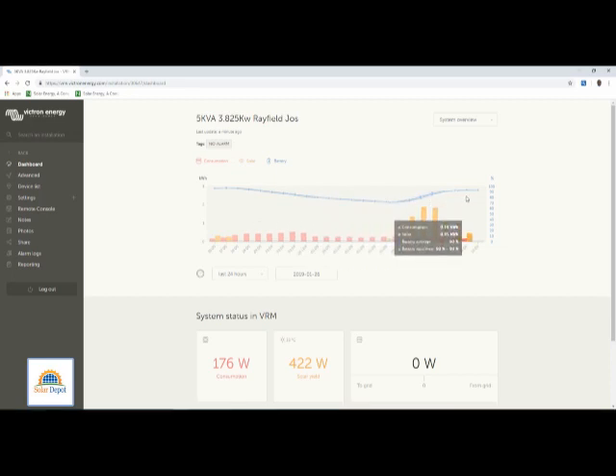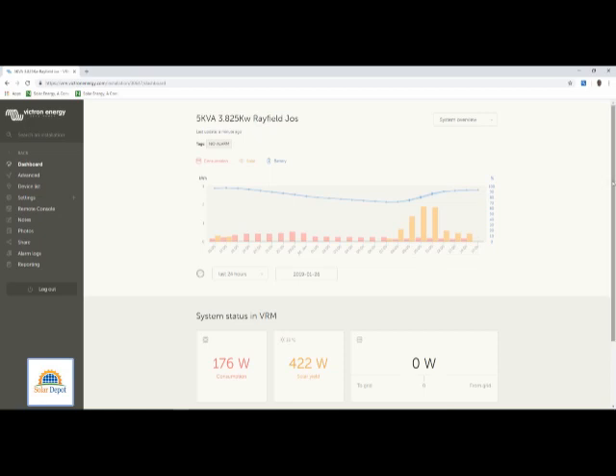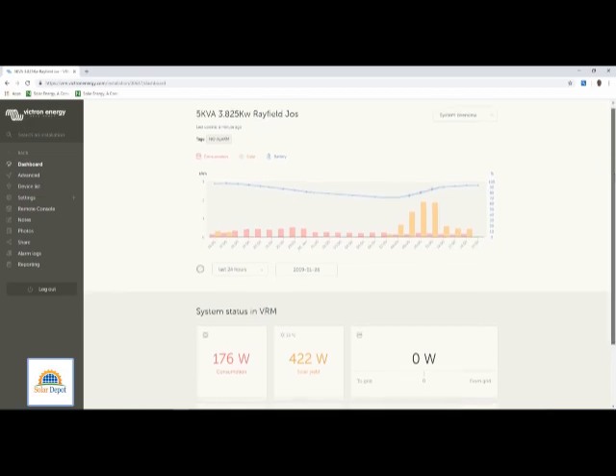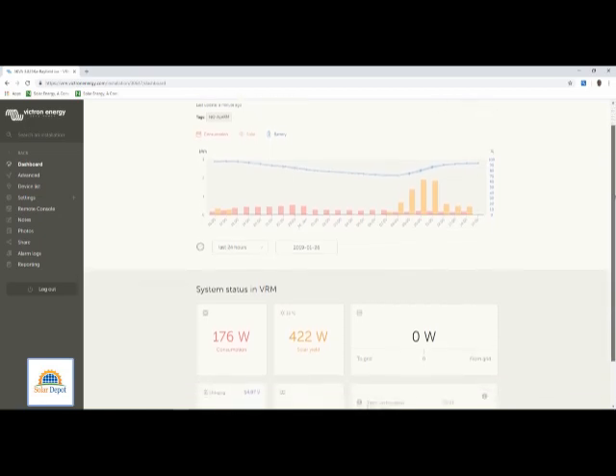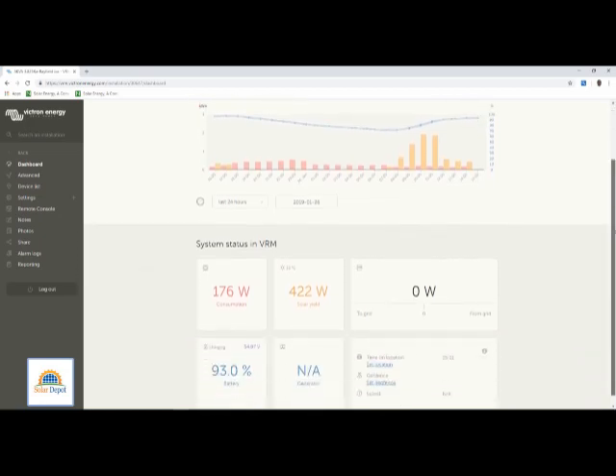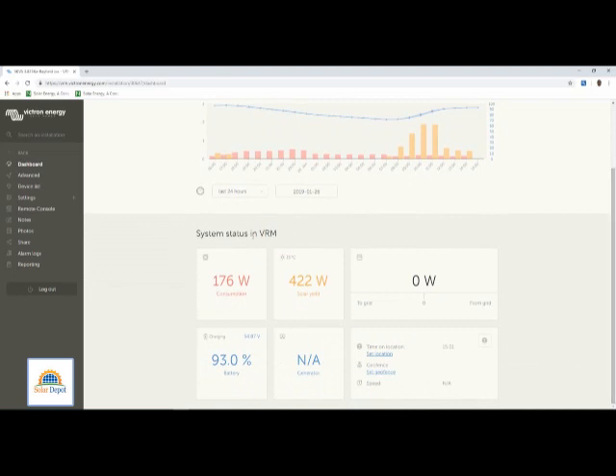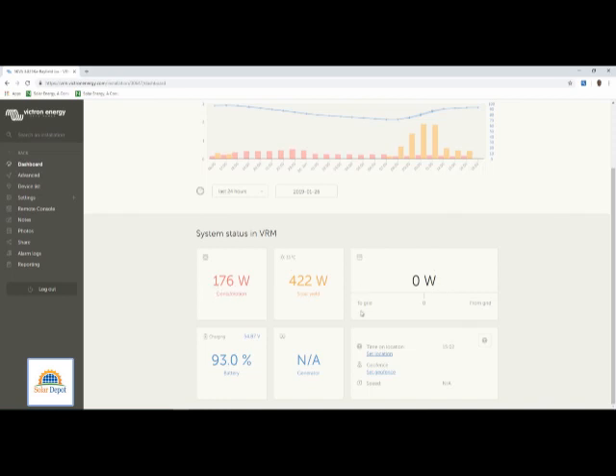Presently, the consumption is 176W. Solar generation is 422W because the batteries are in the absorption stage of the battery charging stages which are bulk, absorption, and float. The grid is 0W because the system is totally off-grid. The battery is 93% charged and no generator is connected.